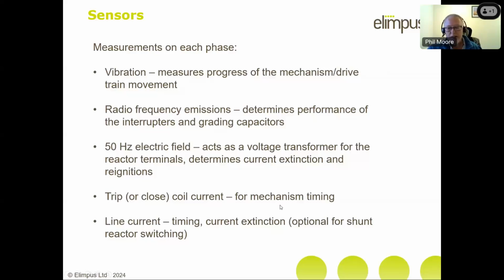We need the trip and the close for mechanism timing, and that's common with all circuit breaker monitoring systems. You might want to have the line current measured. We are increasingly doing this, but on a shunt reactor you don't need it at all. You can see as much as you need to from the electric field signal.